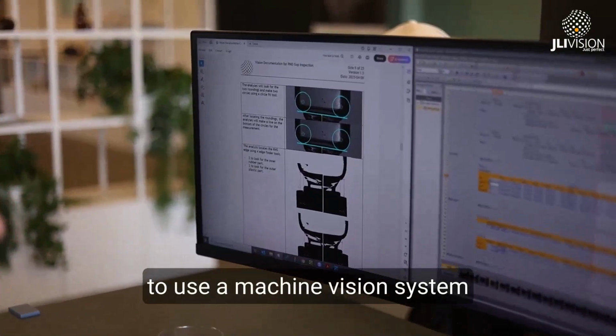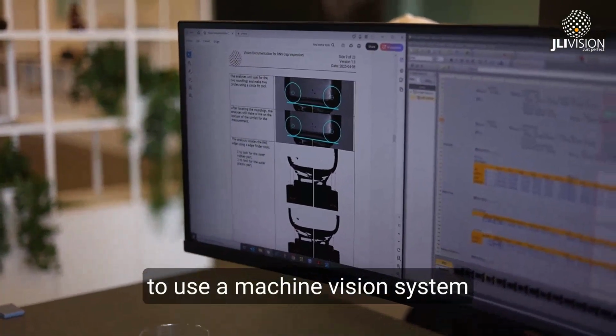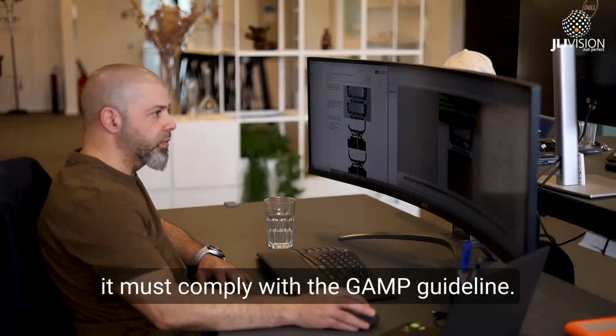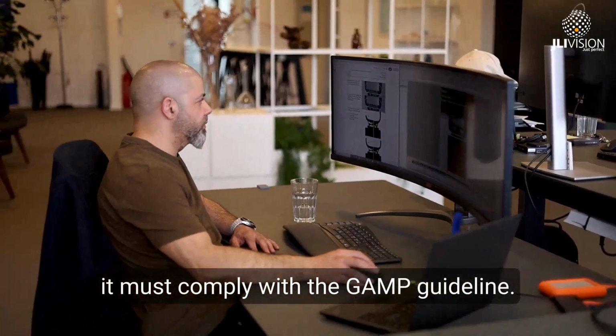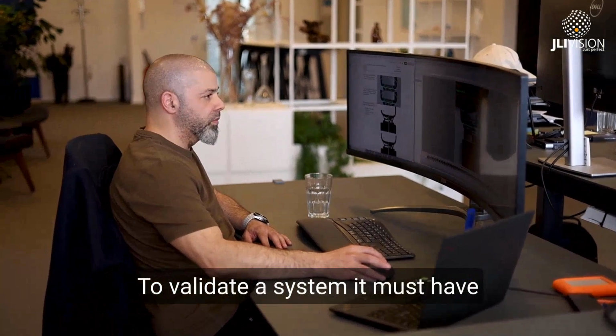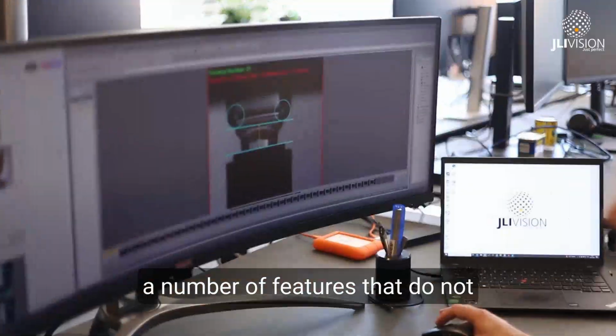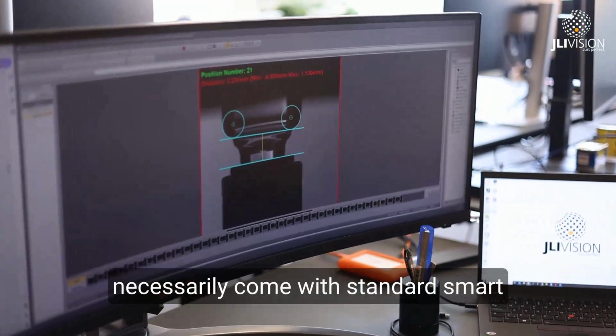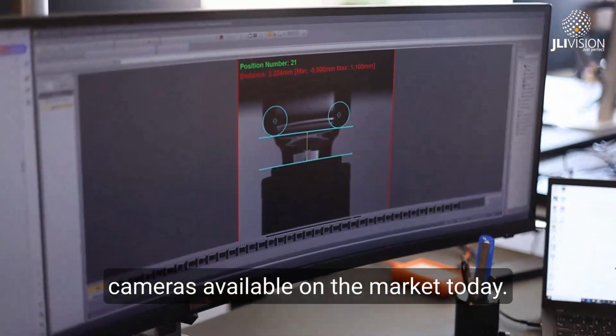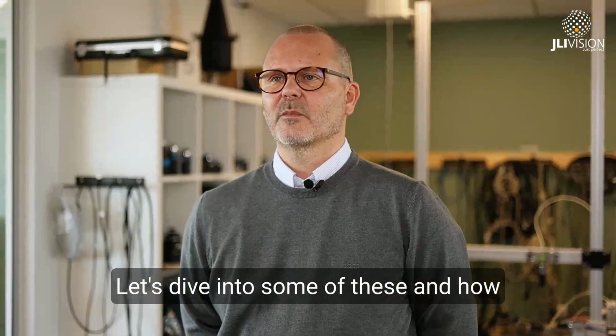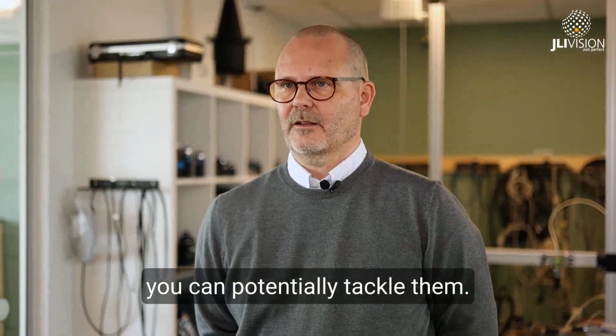In order to use a machine vision system in a validated environment, it must comply with the GAMP guideline. To validate a system, it must have a number of features that do not necessarily come with standard smart cameras available on the market today. Let's dive into some of these and how you can potentially tackle them.